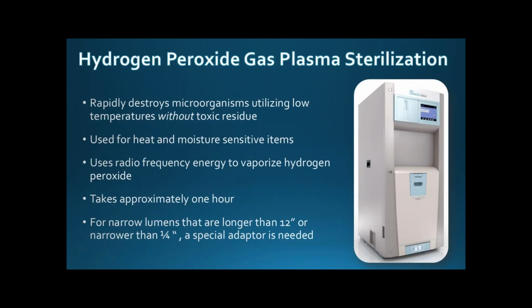Hydrogen peroxide gas plasma. So this is going to be your low heat sterilization methodology, your STERRADs that you have. Again, it's going to have the same requirements for chemical and biological indicators. But how it works is that it's basically going to be used for your heat and moisture sensitive items.